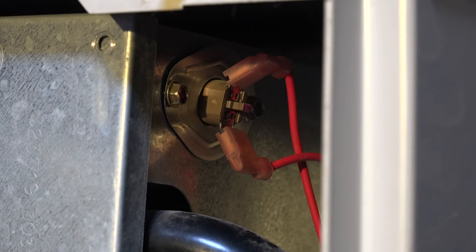It was put in there because the furnace had a rollout. The furnace had a rollout because it had a cracked heat exchanger. So this was the first thing done to repair it. Obviously, that should not have been done.